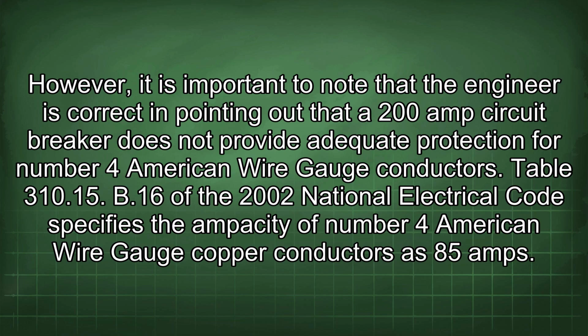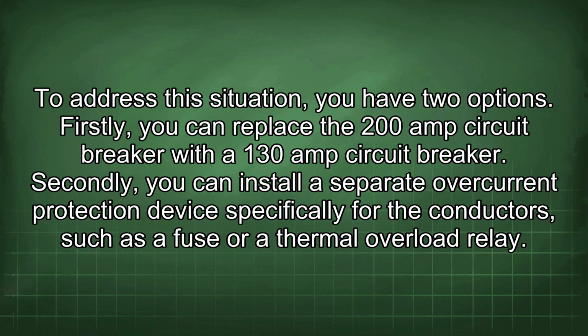However, it is important to note that the engineer is correct in pointing out that a 200 amp circuit breaker does not provide adequate protection for number 4 American wire gauge conductors. Table 310.15(B)(16) of the 2002 National Electrical Code specifies the ampacity of number 4 American wire gauge copper conductors as 85 amps. To address this situation, you have two options.